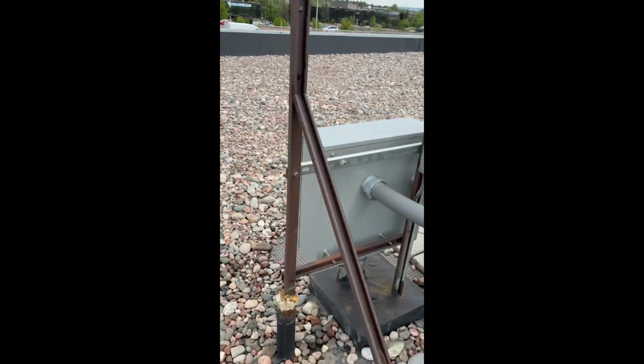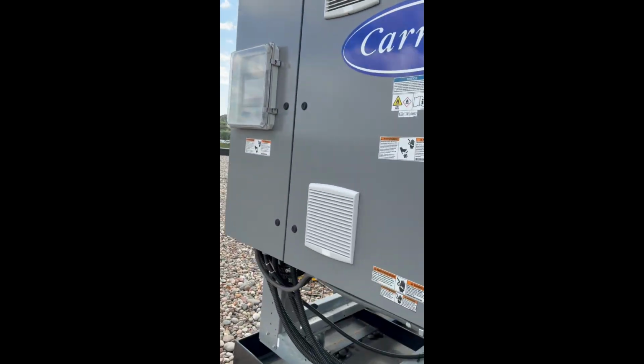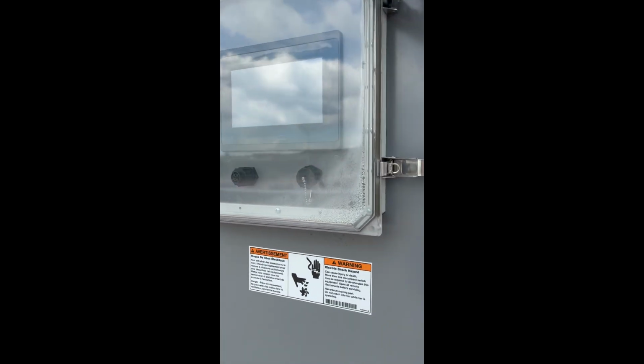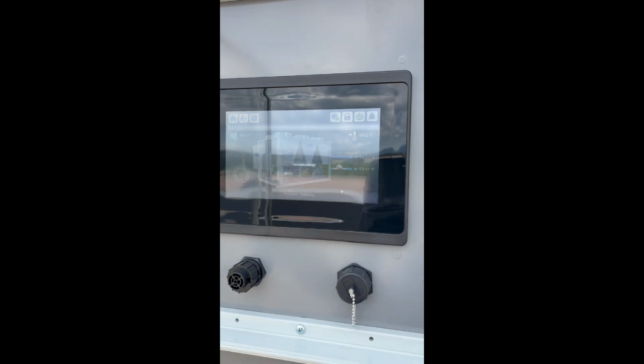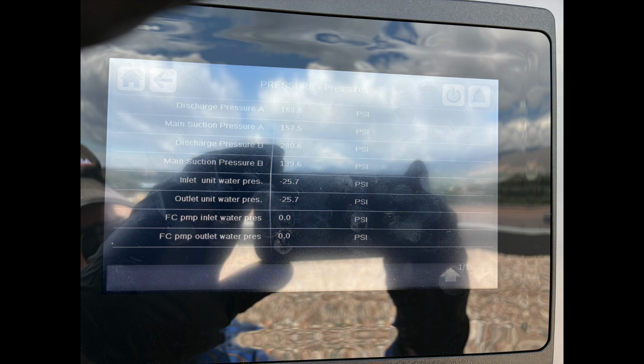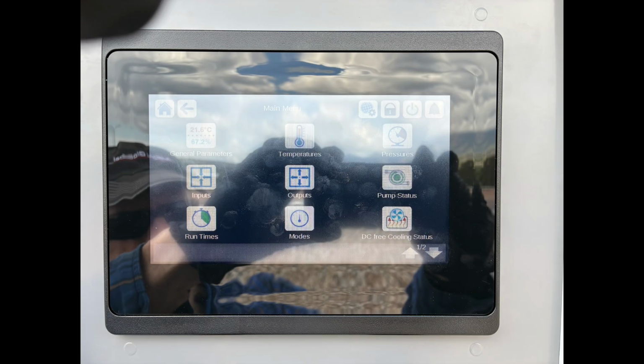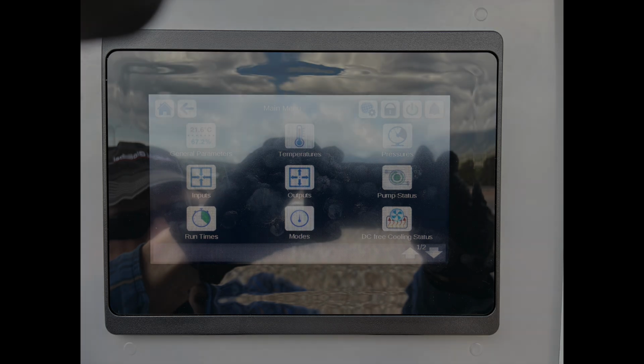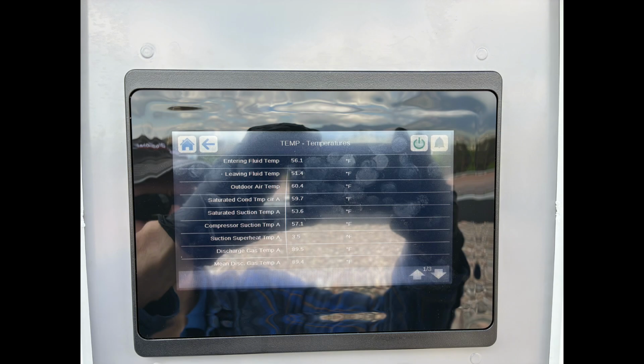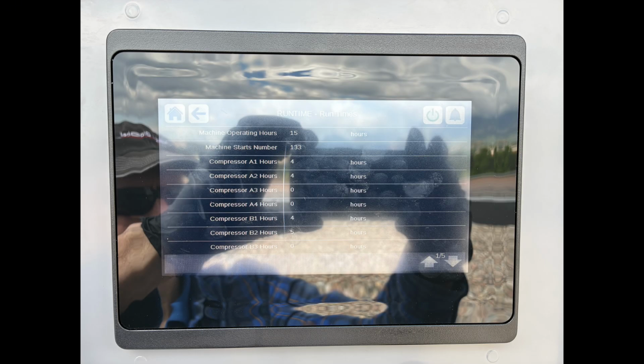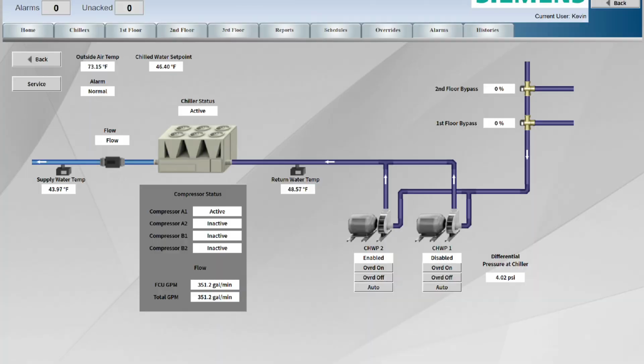So I just want to give you a look at the components of the new chiller. You can see we got a new enclosure, new disconnect switch. This one's nice. It has a touch screen right on the front, so you can monitor what it's doing in real time, make adjustments. So you can read your pressures in real time. See, there's a menu screen. You can read your temperatures in real time. And you can see what your compressors are doing, which ones are on, which ones are off.